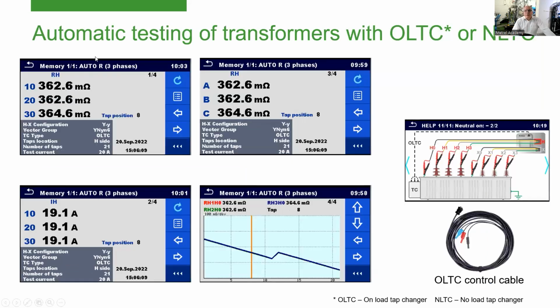If you are testing big transformers which have a motorized tap changer, you can control them also with the help of the instrument itself. So you connect an additional cable, a control cable, from the instrument to the tap changer controller, and you can perform the winding resistance tests of all positions of the tap changer automatically. That means you don't need to switch anything manually, but just set up the measurement correctly.